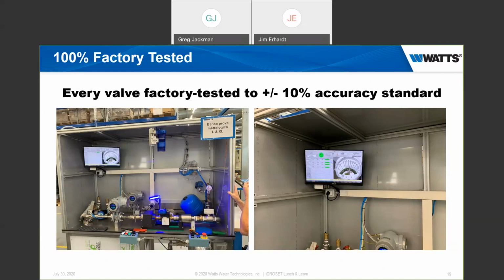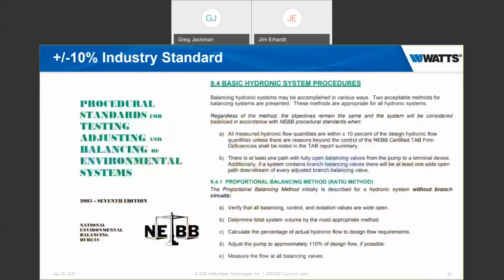On the right is sort of a close-up of the screen. You'll see the happy face on there. The happy face means that valve test passed. And you'll see the 4 readouts there where the flow was taken, and the valve passes, it gets packed up and out the door it goes. So plus or minus 10%. Now, where does that plus or minus 10% come from? Why is that a big deal? Next slide will describe it.